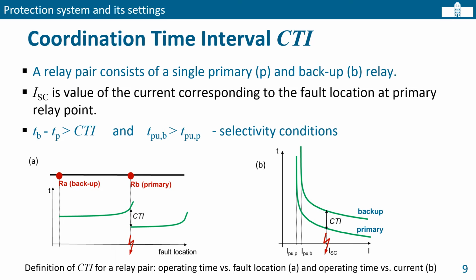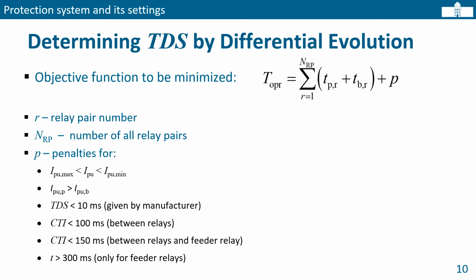To provide proper operation of relay pairs, we have to know that each relay pair consists of a single primary and backup relay. So if we observe this current I that is measured at the primary relay point, then the secondary or backup relay should operate after the time CTI if the primary relay fails. Also, the operation time of the primary relay must be shorter than the time in which the backup relay operates.